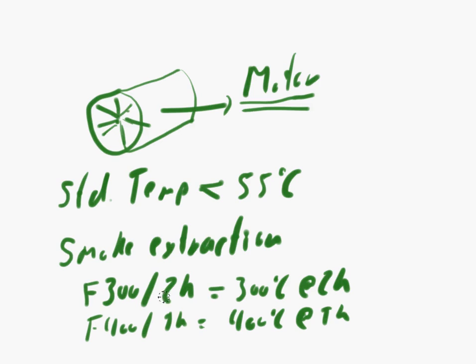If, however, you succeed in that test and your fan withstands, let's say like 300 degrees Celsius for at least two hours, you get that certificate and that means you can sell smoke extraction fans. Smoke extraction fans are very important, especially in buildings and tunnels where there's risk of fire.